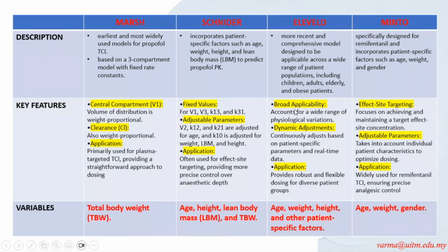And Eleveld has broad applicability, accounting for a wide range of physiological variation: age, height, weight, and so on. Dynamic adjustment: it continuously adjusts based on specific parameters and real-time data. So this is the most evolved pump which I have encountered, but what we have in Malaysia now, it dynamically adjusts. It adds the patient's concentration, and we adjust the rate accordingly. The algorithm evolves and adjusts to the real-time data. Application: provides robust and flexible dosing for diverse patient groups.